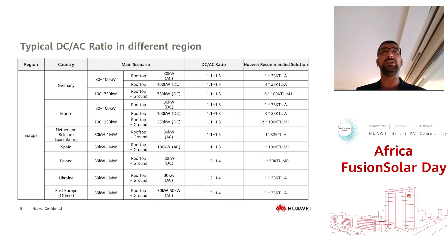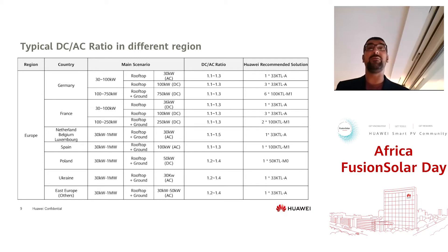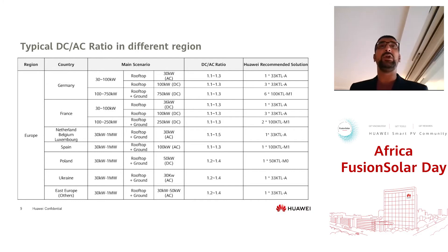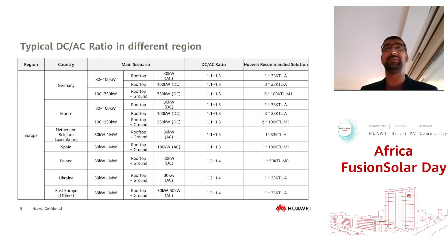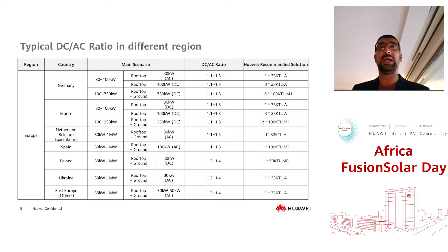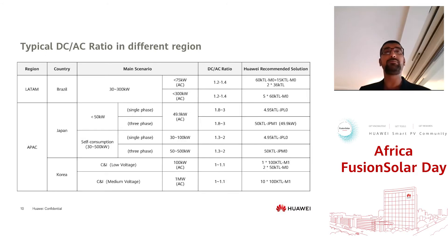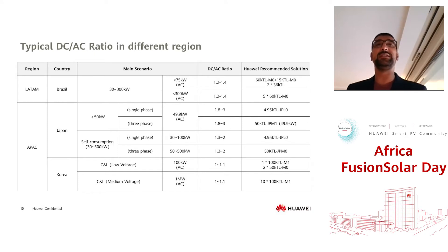Typically, DC to AC ratios differ across geographical locations. For example, in the Southern Africa market you would have a specific DC to AC ratio. In Germany, a 100 to 750 kilowatt rooftop system would have around 750 kW DC, so six of the 100KTL-M1 inverters would be suitable, providing a 1.1 to 1.3 oversizing ratio. We have examples from Latin America and Asia Pacific as well — notably, projects in Japan use quite aggressive DC to AC ratios of 1.8 to 3.